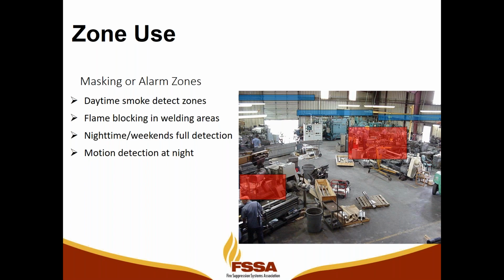So the blue zones are alarm zones for smoke. The red zones are the blocking zones for flame, where welding or cutting are occurring. So say that there's some smoke started in the pallet of paper, with paper down at the bottom of the screen. The smoke rises, it's detected, tracked. As soon as it touches the smoke zone, the system goes into alarm, way before it hits the ceiling. If there's a flame generated on this paper, the system will go into alarm because we're only blocking flame in the two blocking areas.